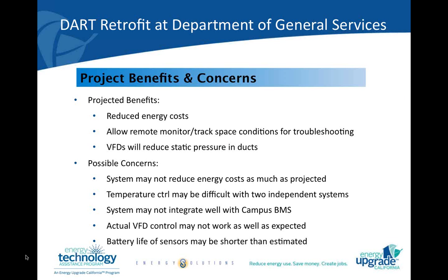The benefits that we're hoping to realize with this particular project are reduced energy costs, the ability for our operations staff to remotely monitor this facility for troubleshooting, and some help with commissioning. And a big thing maintenance staff has been asking for a while is VFDs, because the static pressure runs pretty high certain times of the year on the system. So we're getting those VFDs with this project.